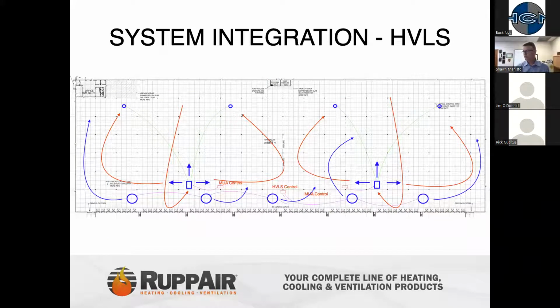So back to the integration slide on the HVLS, we commonly put the HVLS where you're going to have occupancy, dock areas where a lot of people are going to be working. If there was an assembly area back in here, we may put 4 HVLS back in this area, but then also having them interface to an overall control system that can control all the fans independently or as a zone system.